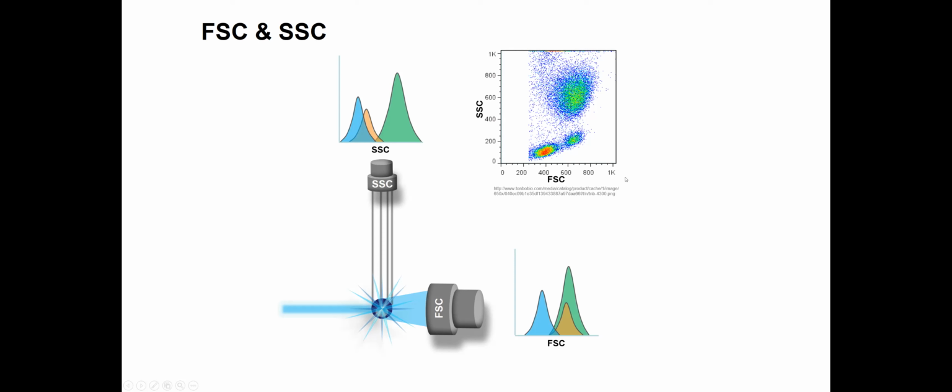This is our blood. Red blood cell is pre-removed by breaking down the red blood cell. Red blood cell is more than 99% of cells. If you plot them together, majority of them is red blood cell. It's very difficult to see. So you remove red blood cell first, and then white blood cells. Now among these, all the scattering can give you the information about the size of the cells. If it's a bigger signal, then these cells are bigger cells. If this is here, this is smaller cells.